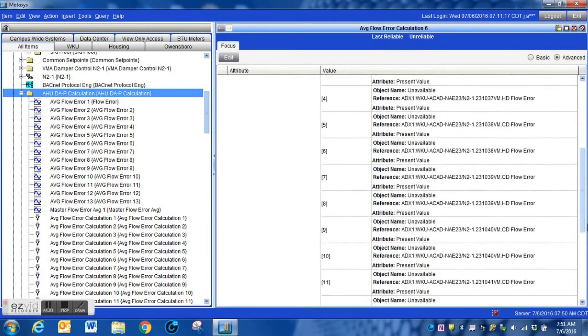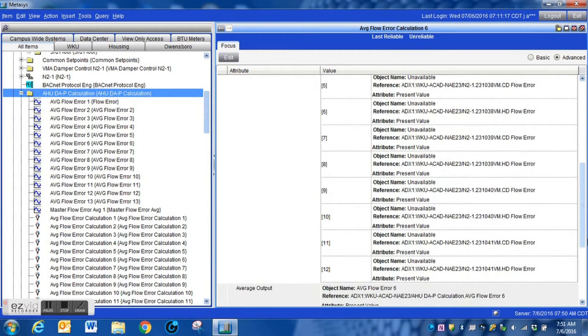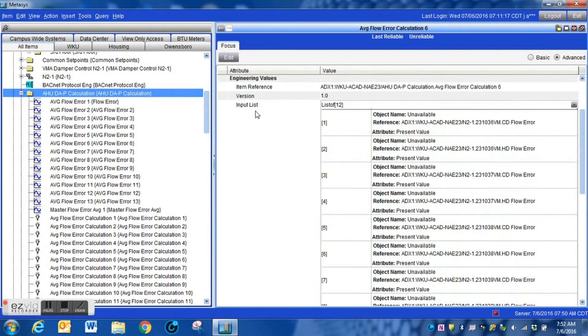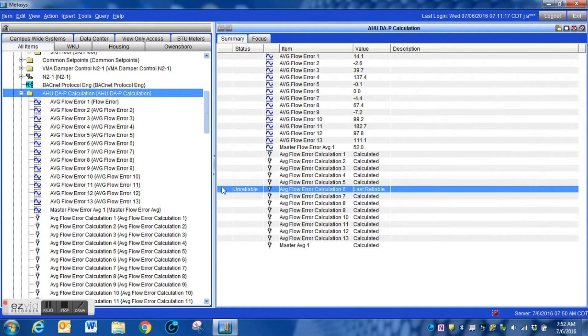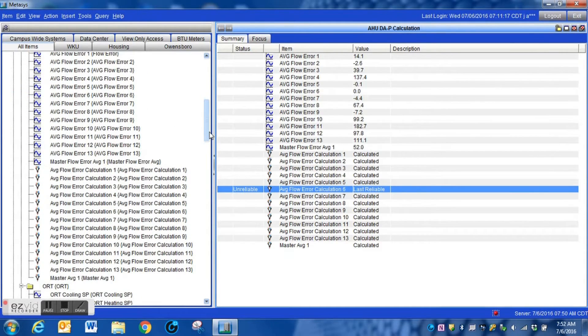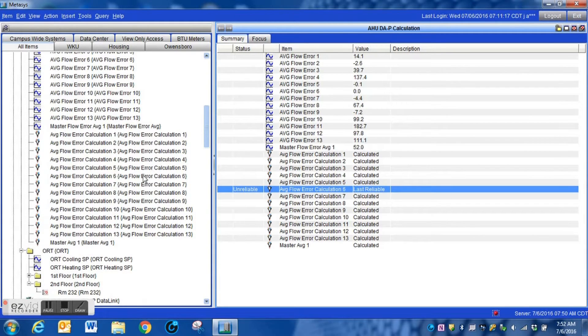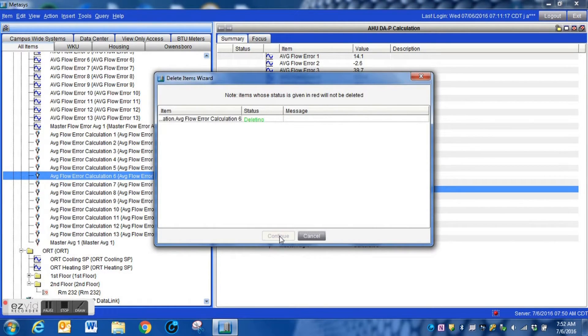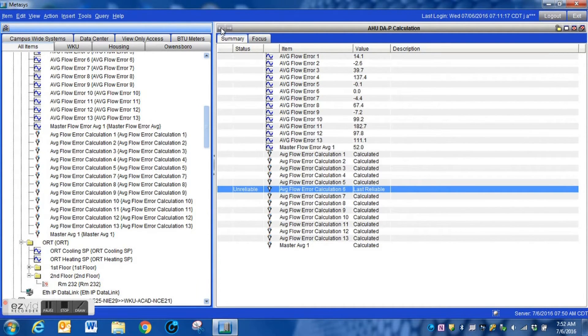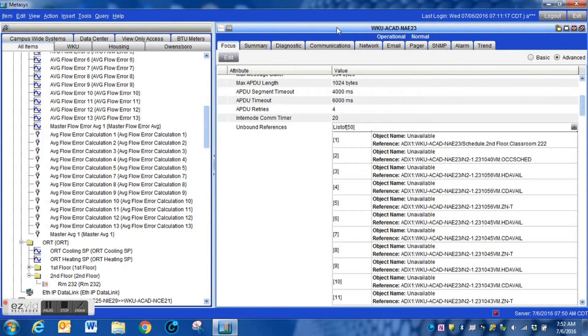You can see here a piece of logic where the slave list was for a common zone temp setpoint. Inside this logic, several items are showing as unreliable because they were connected to those particular controllers that were removed. What we will do is go in and actually remove those controllers from the logic. I'm simply going to hit Delete on this because that whole logic block is no longer used, and away it goes.